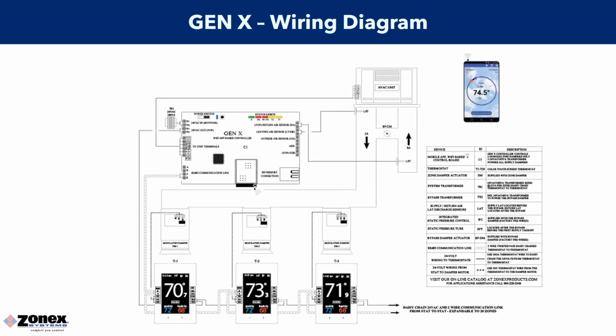Here we have a Zonex wiring diagram that we'll be going over in more detail. The Zonex controller should be installed inside the conditioned space and accessible to any personnel, IT people, or anyone that might need to get to it for ongoing maintenance purposes. The Zonex controller is a 2-heat, 2-cool gas operation controller or a 2-cool, 3-heat heat pump operation controller. The Zonex is powered by an independent 24-volt 100 VA transformer that wires up to the TR1, TR2 terminals in the left-hand corner of the board. Please note we are polarity sensitive and we want to make sure that the hot leg of your transformer wires into the TR1 terminal.